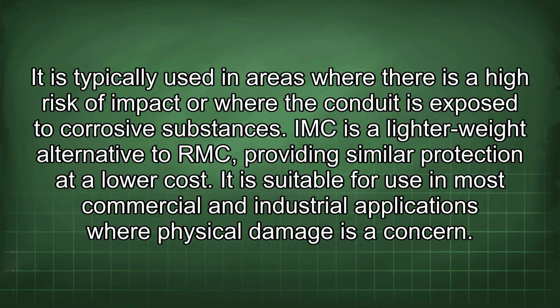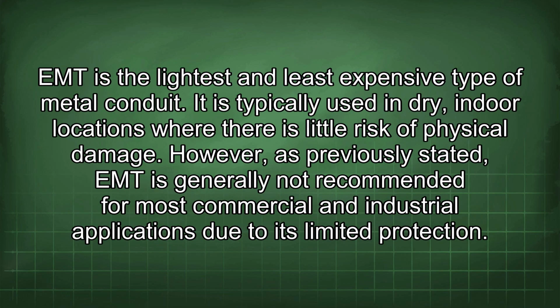It is suitable for use in most commercial and industrial applications where physical damage is a concern. EMT is the lightest and least expensive type of metal conduit. It is typically used in dry, indoor locations where there is little risk of physical damage. However, as previously stated, EMT is generally not recommended for most commercial and industrial applications due to its limited protection.